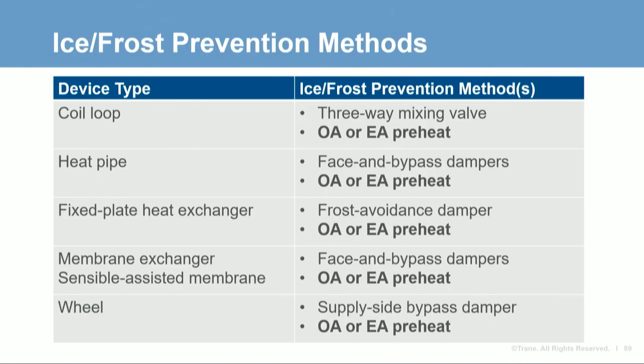Even though the SAM exchanger has higher sensible effectiveness compared to a metal plate exchanger alone, the latent transfer through the membranes and the orientation of that transfer removes the risk of icing. A SAM exchanger with 75% sensible effectiveness will operate at conditions where a sensible-only plate exchanger would need to reduce recovery to prevent ice. The methods of ice/frost prevention described each involve reducing heat recovery capacity — meaning less energy savings during the coldest times. As an alternative, any technology could use a preheat coil to warm either outdoor or exhaust air before it enters the device. Preheating the exhaust air can result in less overall heat required and doesn't risk coil freezing if hot water is used.